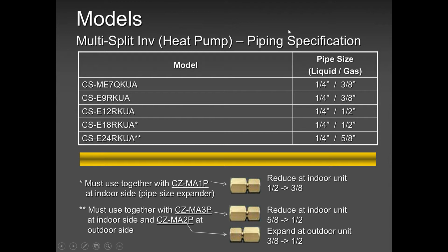In our case, for a 7,000 or a 9,000, you will run all the way quarter and 3/8, because our outdoor unit has only one size, 3/8 on the suction line and quarter on the liquid line. So for the 7,000, the 5,000, and the 9,000, you don't need any adapters. Okay, guys? But for the 12, 18, and 24, you need adapters. For the 12 and 18, listen carefully, guys. Because the indoor section is 1/2 inch and quarter, you will run quarter and 3/8 all the way to the indoor unit.